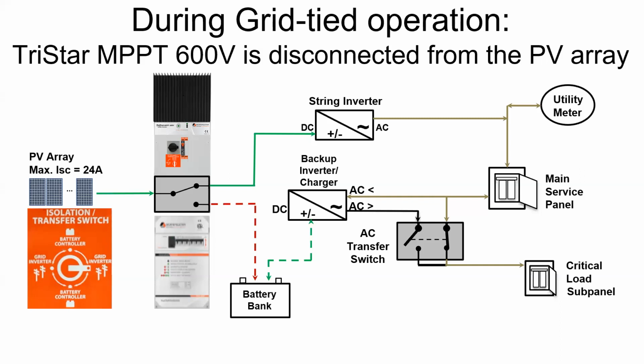From a retrofit standpoint, it becomes very cost effective to keep your string inverter. Your existing PV array is wired to 600 volts max. You don't have to do anything. You don't have to change anything about your existing grid-tied operation. You still have your PV array. It's feeding your string inverter, powering loads at the main AC panel, backfeeding the rest to the utility. And that's it. Now, by adding in our 600 volt charge controller equipped with the DC transfer switch, we can preserve that efficiency of the string inverter in just straight conversion, DC to AC, straight through to the main AC panel.